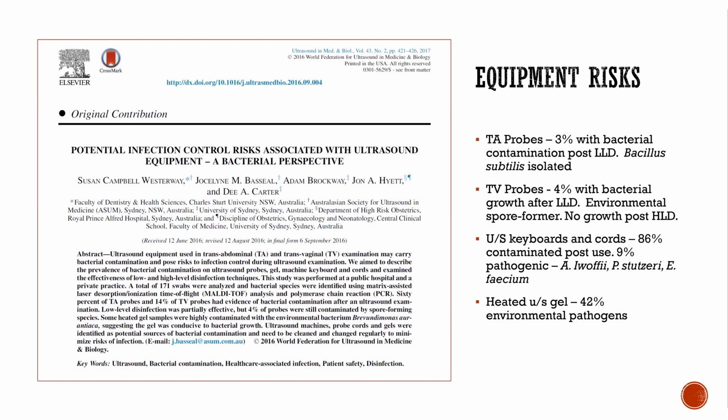The heater station was always just covered in gel and dirty, and I was rounding with a consultant who had come for survey prep, and she picked up one of the bottles. It was super hot, and when she picked it up and squeezed it, it exploded over her, so that was an immediate needing attention item.